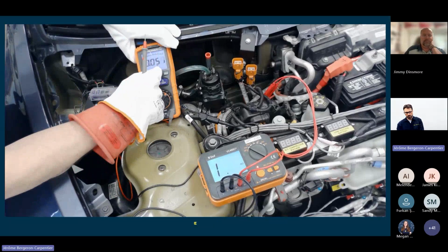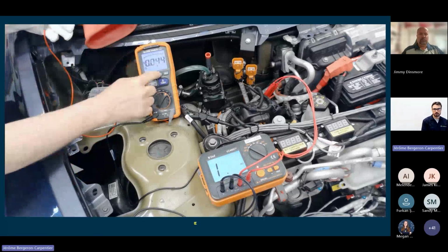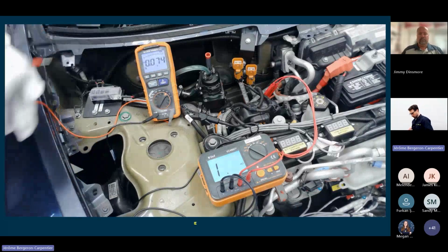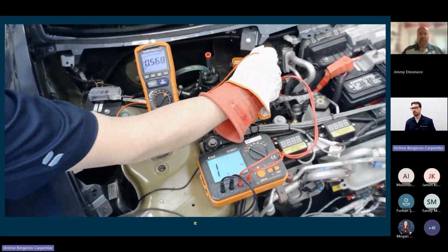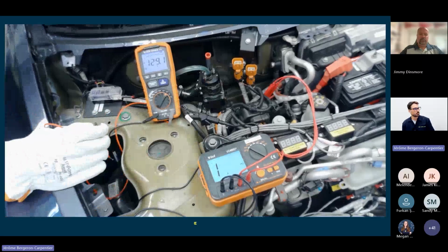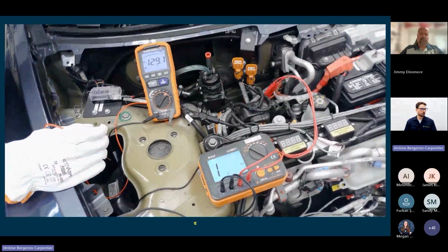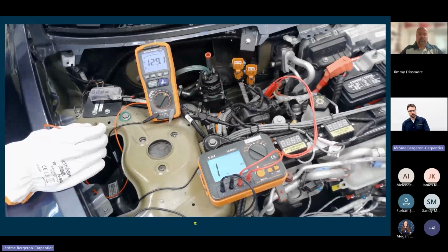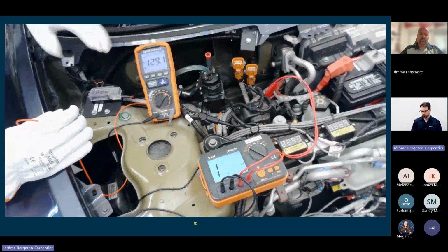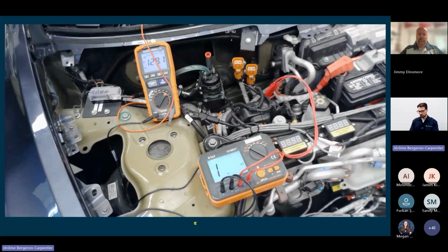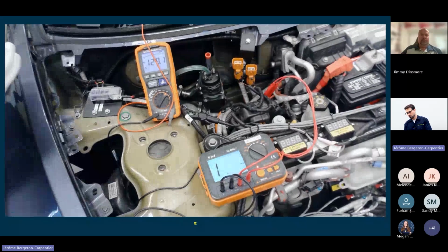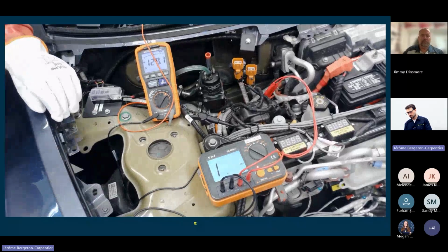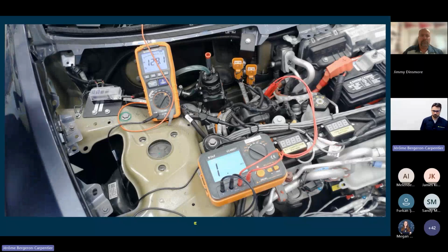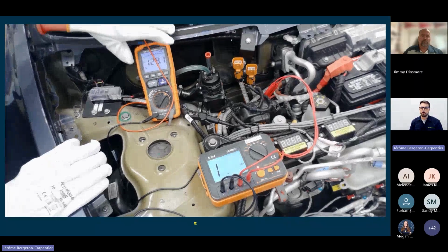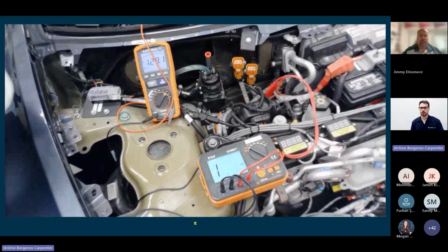voltage. I'm going to turn the screen on here and set my min-max on the screen. I'm going to hit min-max here. So I've got my max reading, and all I'm going to do is go to the connector and touch it, and we're going to see that we have 129 volts stored in the capacitor on that unit. Now, mind you, it discharges extremely fast, especially if I leave my meter on it, because the impedance of the meter will draw down that voltage. But if you're not aware of that, you can wind up taking this apart and creating a small spark, getting a small shock, which could scare you. So it's important to make sure that you follow the procedure for how to do an isolation test when you're testing a high voltage component.